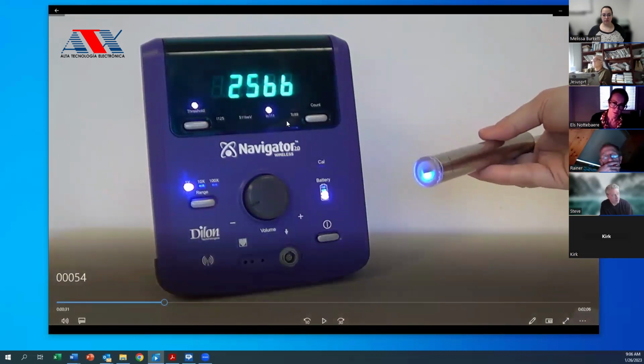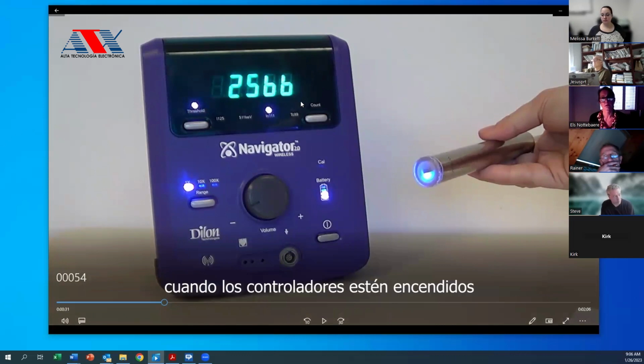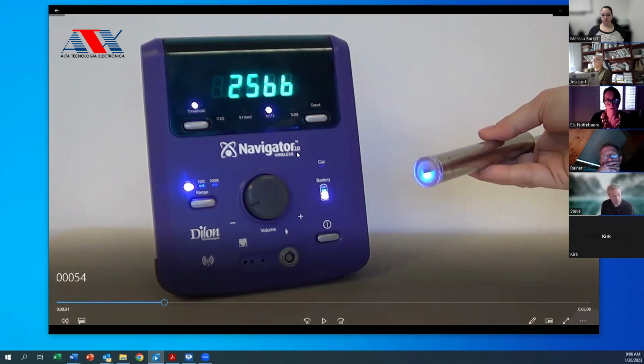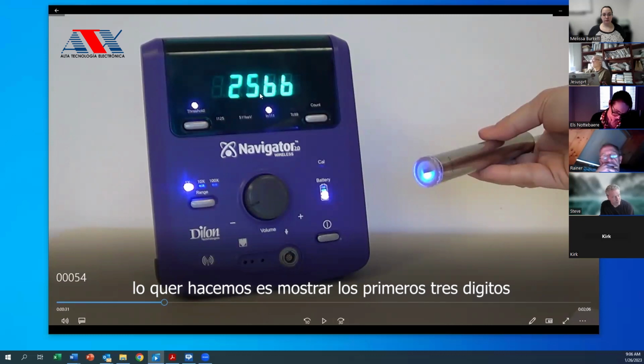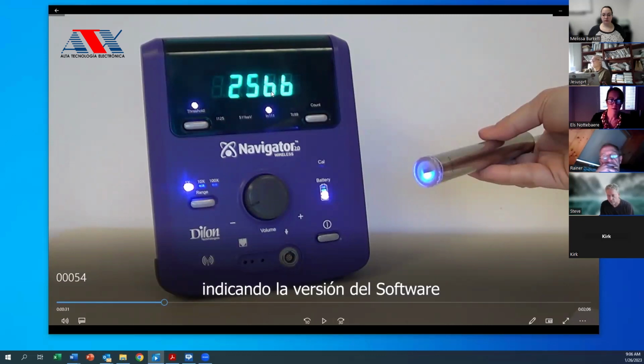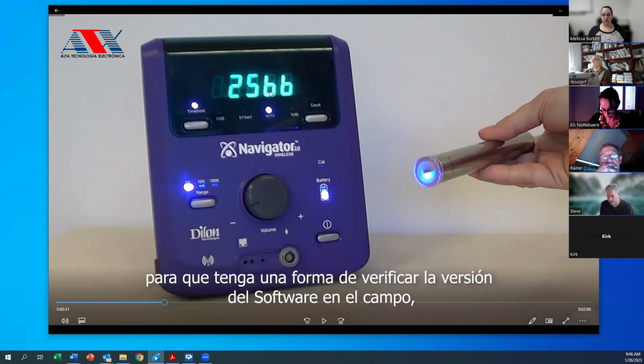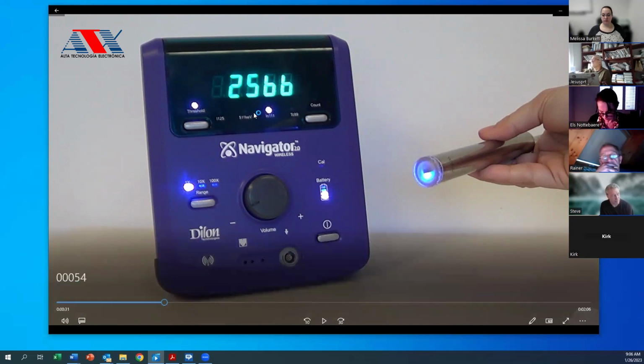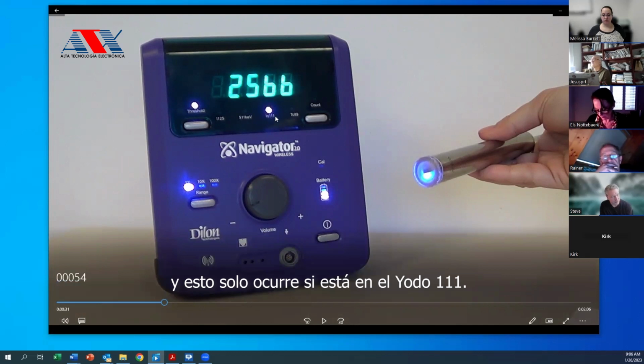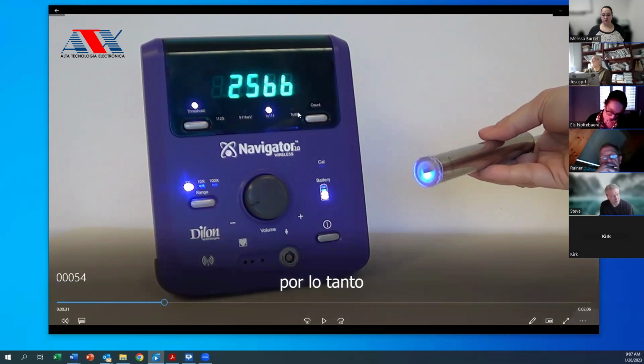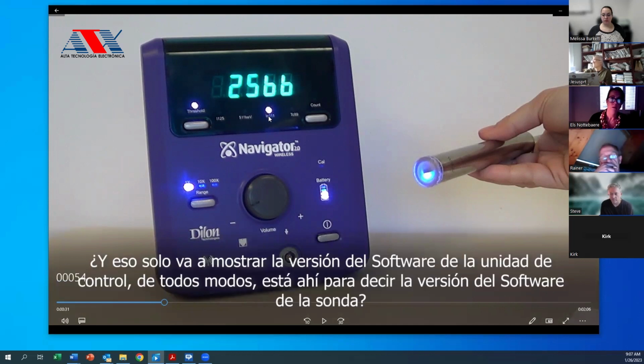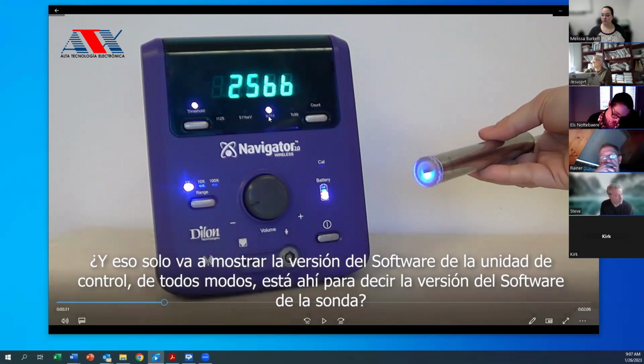When the controller is powered up, if the isotope is indium 111, we show the first 3 digits to indicate the software version. So you have a way to check the software version in the field, but that only occurs if you're on indium 111. If you're on TC99 or another isotope, it only shows on indium 111, and that only shows the software version of the control unit.